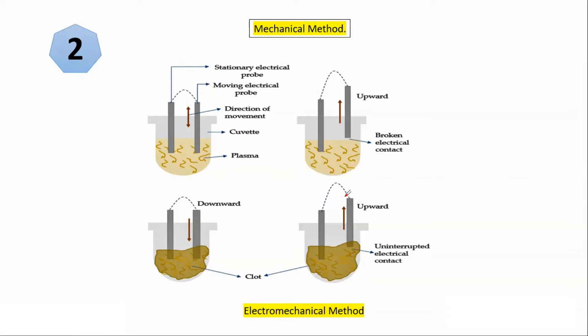So guys in this method we are using electromechanical system. Here one electrode or one probe, electrical probe, is fixed at position and one is free to move or free to oscillate. So here what will happen is we put all the reagent stuffs in a cuvette and these probes, one is fixed inside it and one is free to move or free to oscillate.